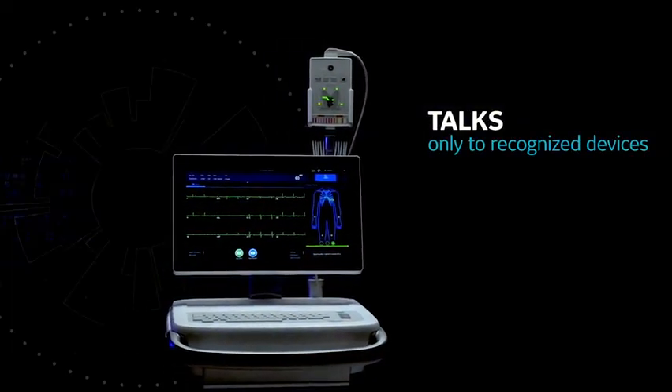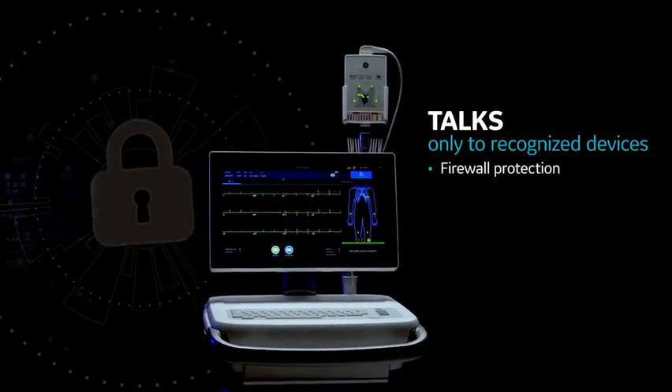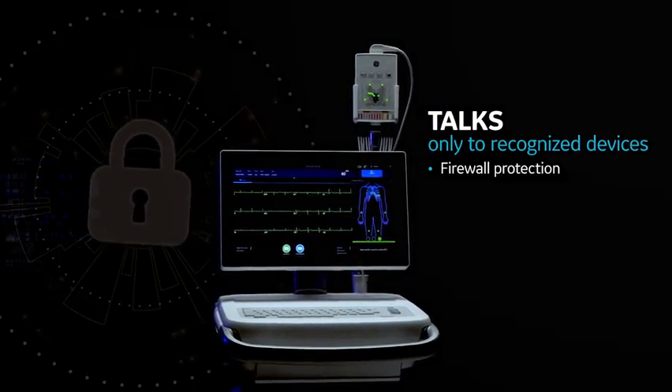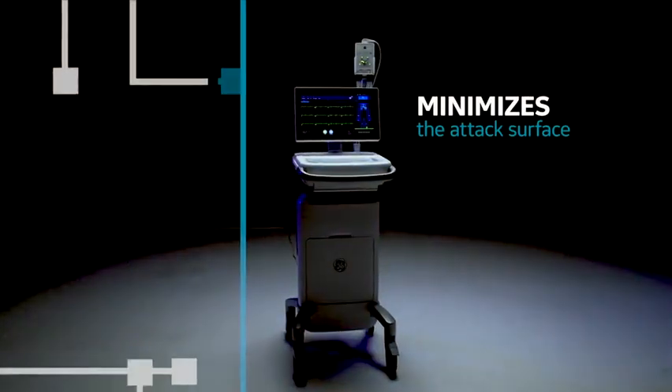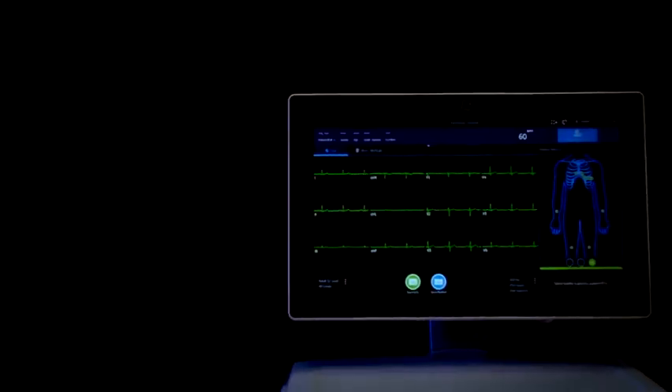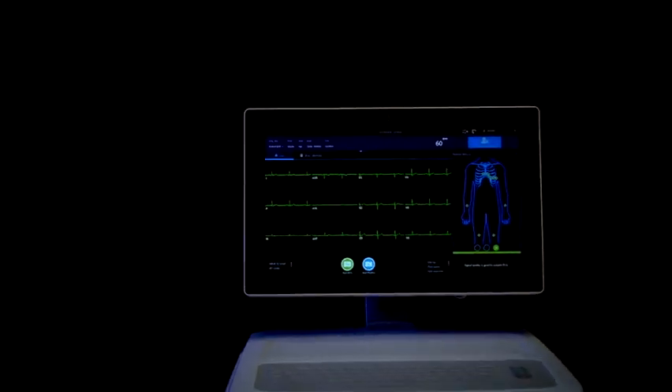MAC VU360 allows you to block unsolicited network traffic by prohibiting communications with unauthorized devices. It also helps minimize the threat of attacks by removing or disabling all operating system services not needed to run the ECG applications.